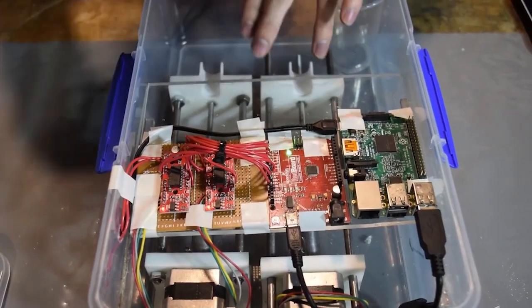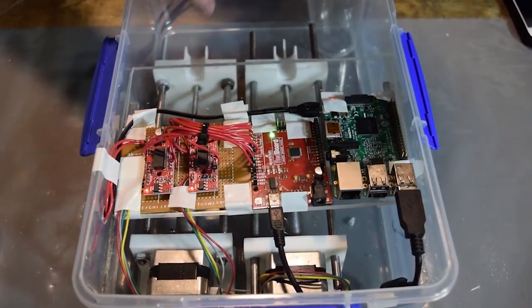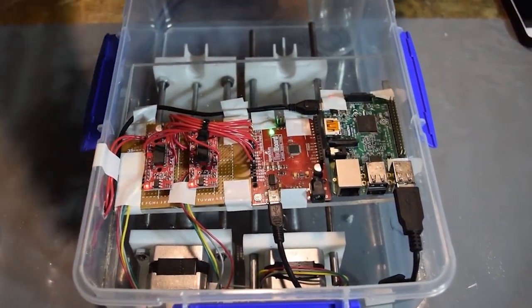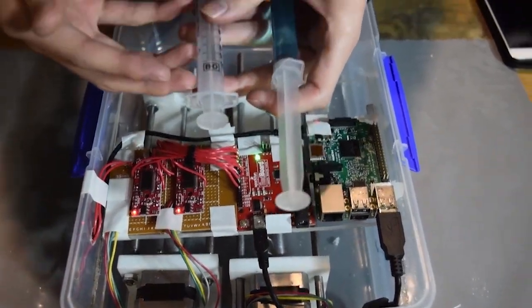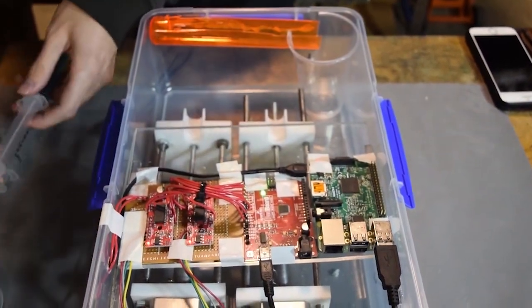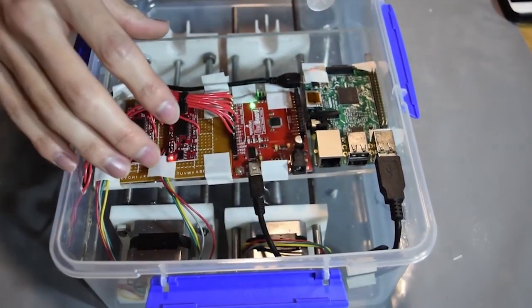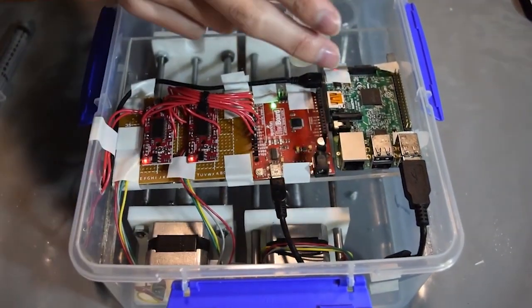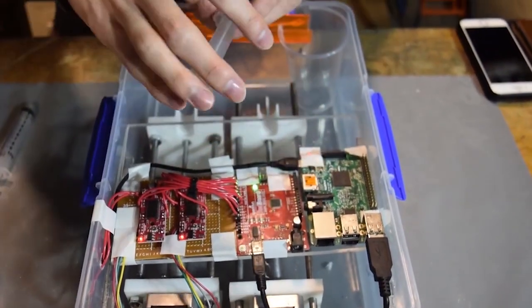These stepper motors are used to empty syringes with these syringe pumps. So what these syringes will be filled with is one of them will have a standard solution and one of them will have a titrant in it. And then what we can do with the drivers and the stepper motors is empty these syringes at a very controllable rate.